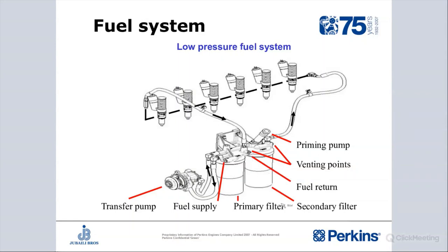Before the fuel is drained back to the fuel tank, it will go through a fuel cooler to cool it down, because we are not supposed to have fuel temperatures exceeding 55 degrees Celsius. What happens if the fuel temperature exceeds 55 degrees Celsius? The fuel burning efficiency will go down. That's why we need to maintain fuel temperatures below 55 degrees Celsius by cooling the fuel through a fuel cooler before it goes back to the fuel tank.